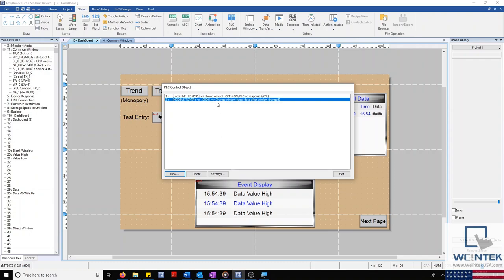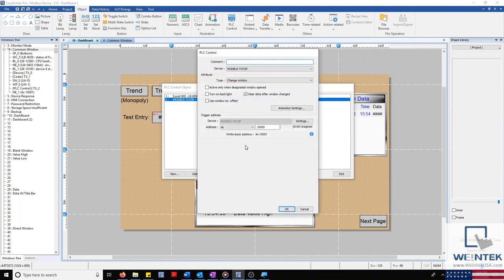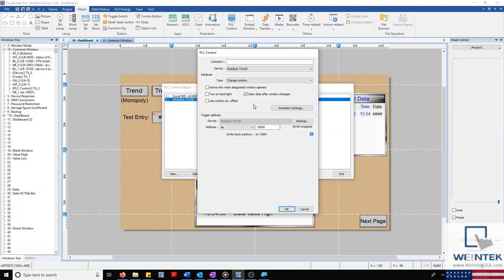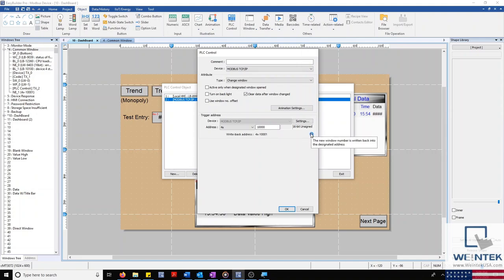Let's look at the settings of my current PLC control object. This object will allow me to change the current display window of my project from my external device by entering the window number into my trigger address. The HMI will then perform the action, as well as clear the data in our trigger address, if it's selected, and then write the new window number into our write-back address.